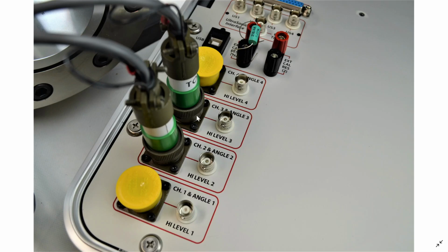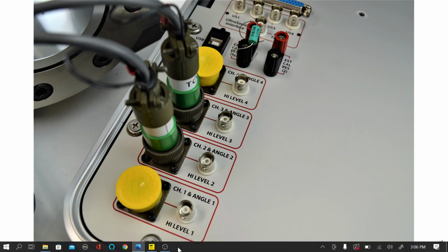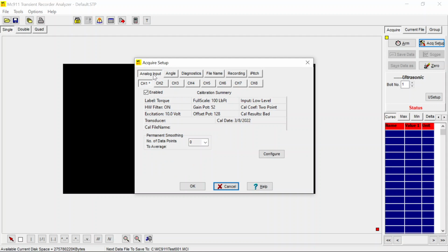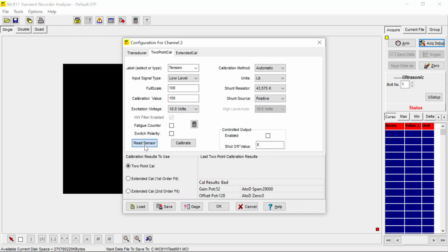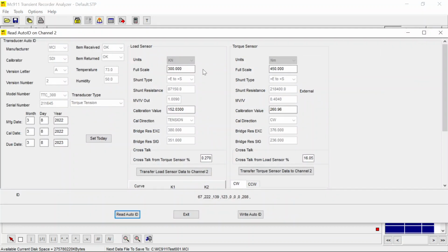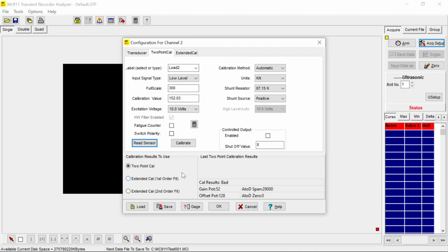Now let's see how we're going to use this. Starting with the MC911, we go into analog input. We have it on channel 2. We can configure and read the sensor. When we read the sensor, it reads two things: the load sensor and the torque transducer. Our channel 2 is associated with the load sensor, which is connected to load. So in here, we have all the information. We transfer to channel 2.